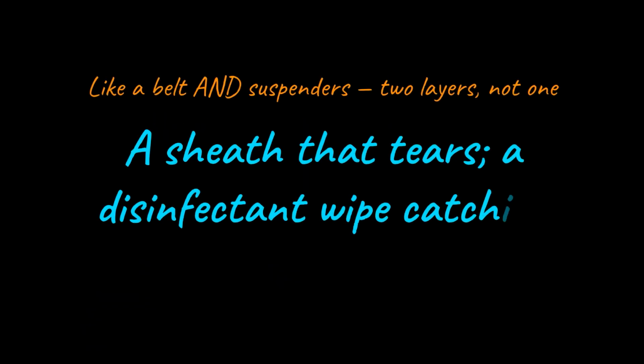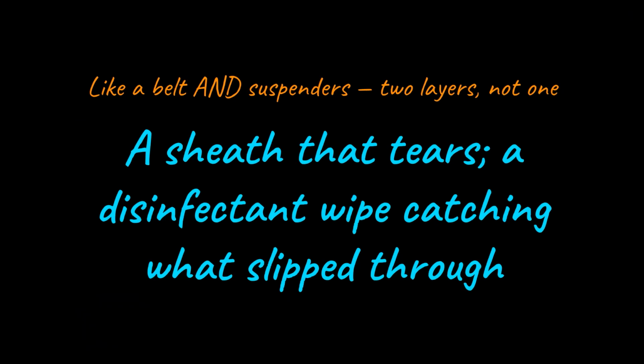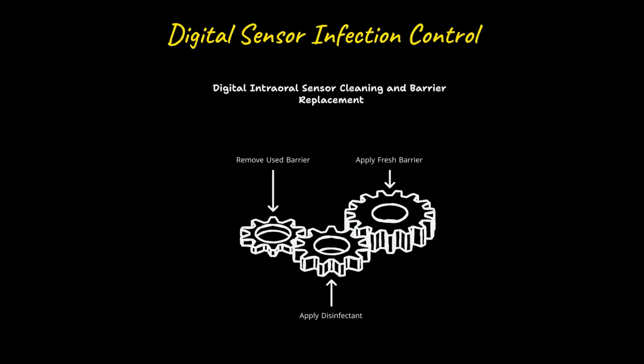This belt and suspenders approach exists because sheaths can tear, leak at a seam, or be breached during handling. Routine disinfection ensures that a small barrier failure never becomes a failure of infection control. The disinfectant used must be one the manufacturer approves. The wrong chemical can damage the sensor surfaces or electronics. The device must never be heat sterilized or soaked, as immersion and high heat will ruin it.